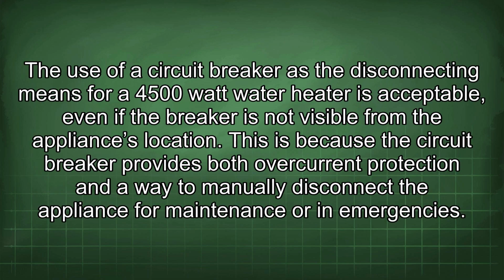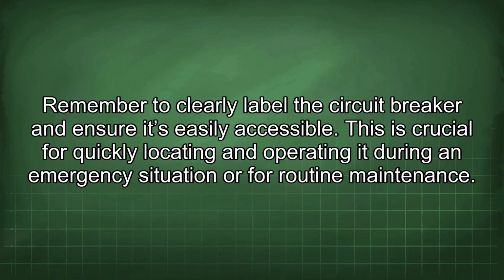The use of a circuit breaker as the disconnecting means for a 4,500 watt water heater is acceptable, even if the breaker is not visible from the appliance's location. This is because the circuit breaker provides both overcurrent protection and a way to manually disconnect the appliance for maintenance or in emergencies. Remember to clearly label the circuit breaker and ensure it's easily accessible. This is crucial for quickly locating and operating it during an emergency situation or for routine maintenance.